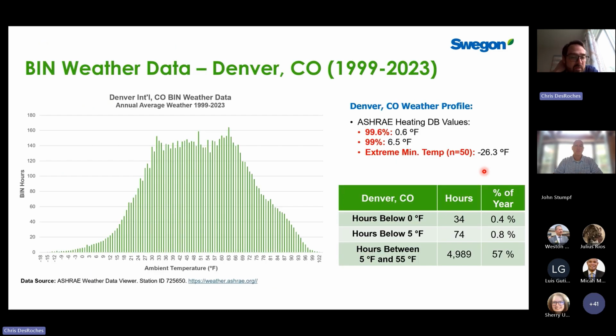Maybe next time I'm invited to present, we'll talk in a little more detail about sizing, but looking at the weather data for Denver, John and I thought this was important to talk about as well. Most of the heat pump jobs, even though we can operate down to -4, are sized for 5F, sometimes 14, really sizing for the cooling requirement and supplementing with backup gas or electric boilers for the other hours. It just comes down to balancing the impact that you're going to have for carbon reduction and energy savings versus first capital cost for the equipment.